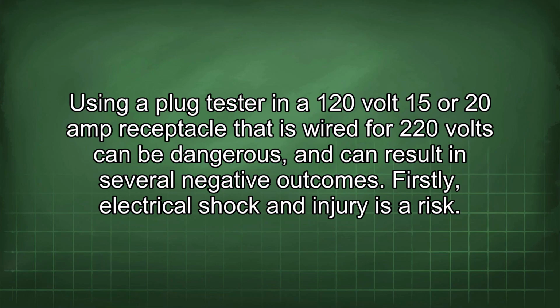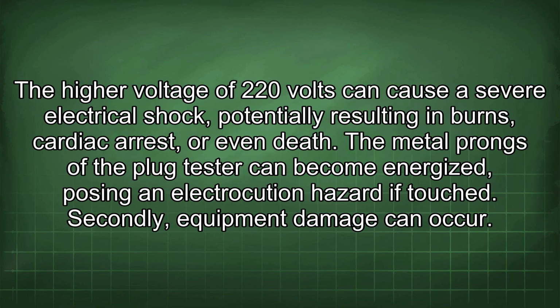Using a plug tester in a 120 volt 15 or 20 amp receptacle that is wired for 220 volts can be dangerous and can result in several negative outcomes. Firstly, electrical shock and injury is a risk. The higher voltage of 220 volts can cause a severe electrical shock, potentially resulting in burns, cardiac arrest, or even death. The metal prongs of the plug tester can become energized, posing an electrocution hazard if touched.